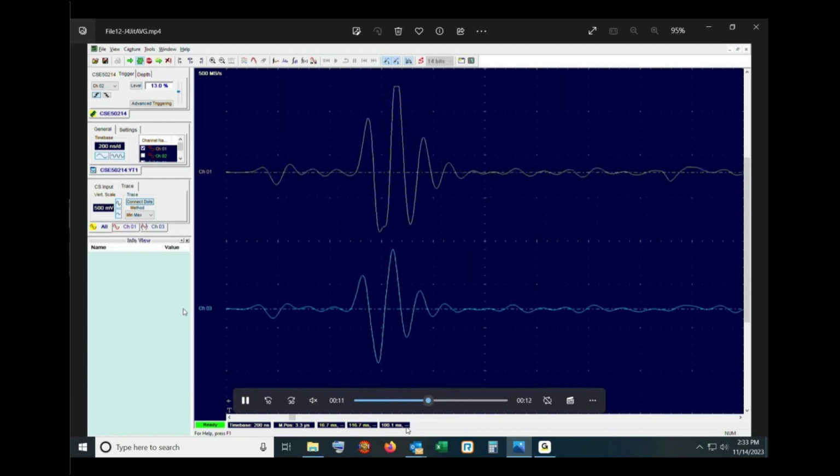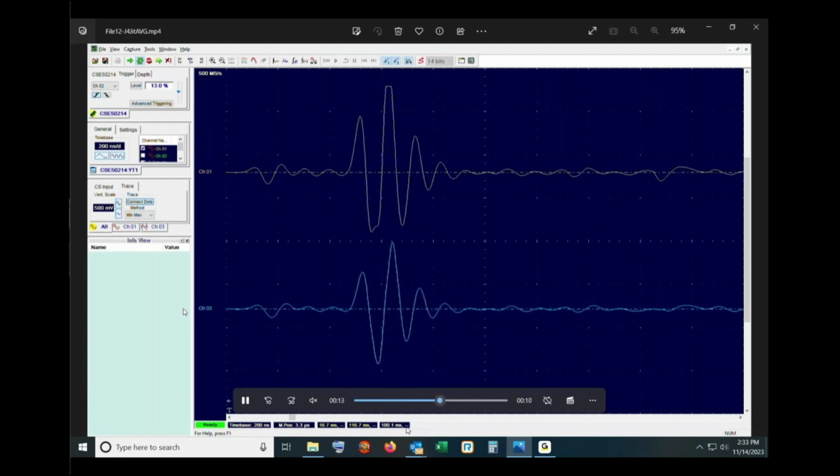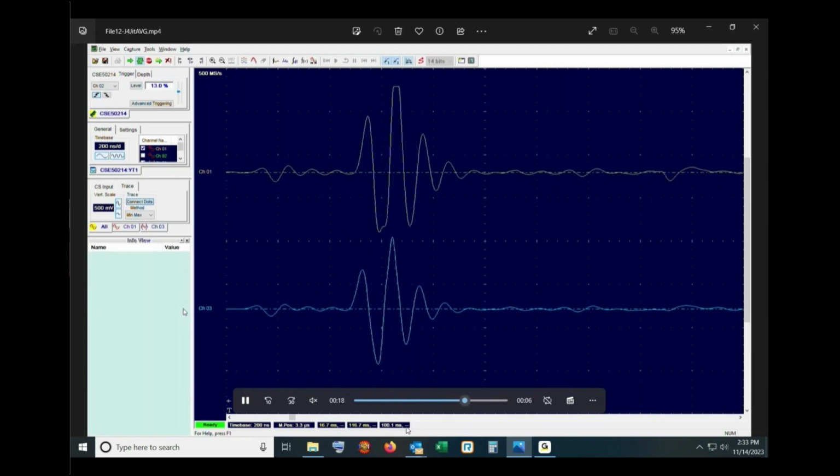So this illustrates the power of signal averaging in ultrasonics. The downside is I can't move as fast because I'm not just taking one waveform per position, let's say. I have to take 400. That illustrates a general principle that the longer I measure, the better measurement I get. This translates into, the higher sampling speed you want, the less maximum resolution is available, typically.